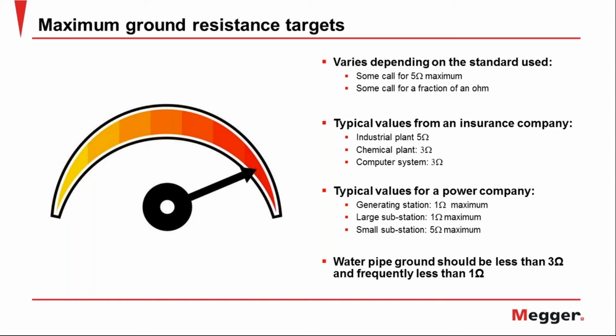So in general, there is no other prevailing national authority. It is often a good idea to have an authority, especially if you're preparing reports for a client or someone like that. But if you do want to cite some sort of authority, then look at your industry. Different industries, like nuclear for instance, they're going to tell you how they want their nuclear facilities grounded and so forth. So look at your industry, look at relevant authorities, and you can get numbers if you want to put it in a report that says such and such an authority said that this facility needs to be grounded at 3 ohms, no more than 3 ohms. So you've got 2.5, and you know, everything looks good.